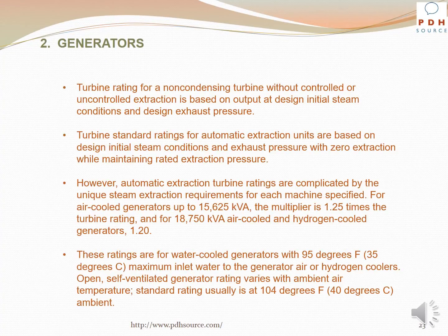Turbine rating for a non-condensing turbine without controlled or uncontrolled extraction is based on output at design initial steam conditions and design exhaust pressure. Turbine standard ratings for automatic extraction units are based on design initial steam conditions and exhaust pressure with zero extraction while maintaining rated extraction pressure. However, automatic extraction turbine ratings are complicated by the unique steam extraction requirements for each machine specified.